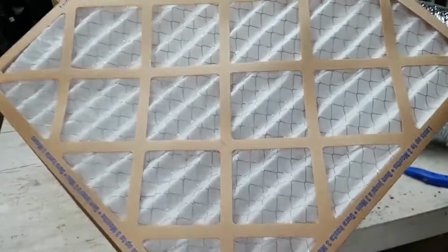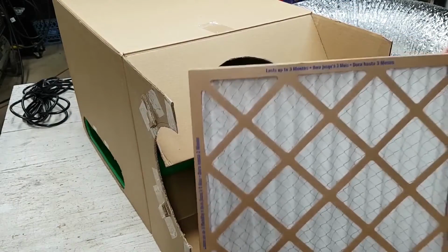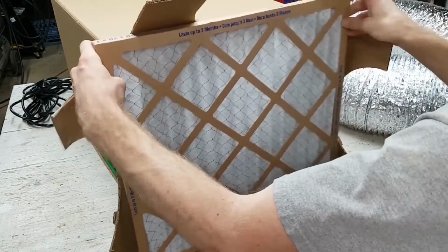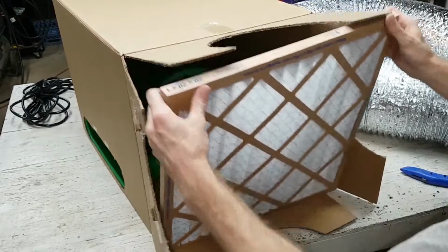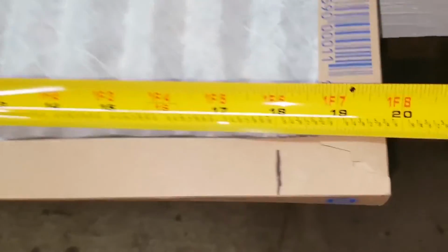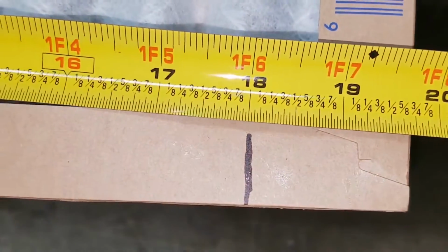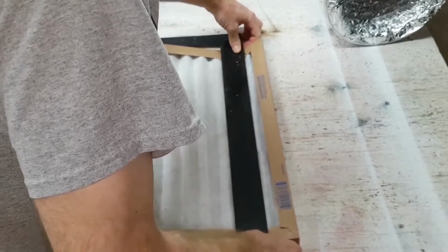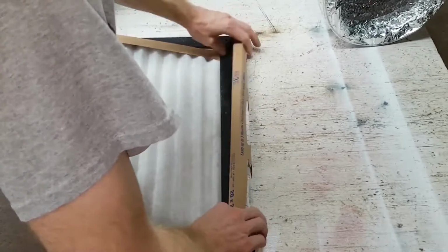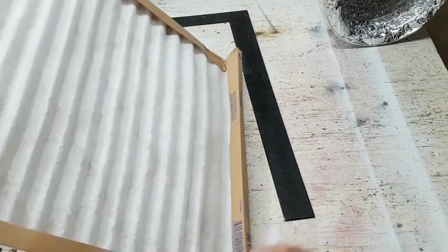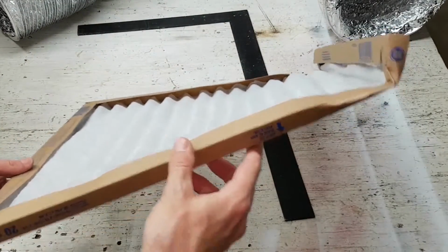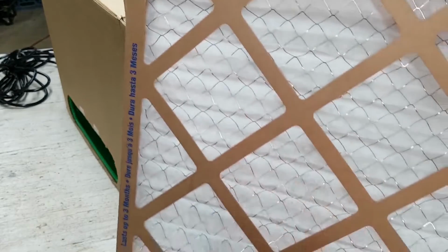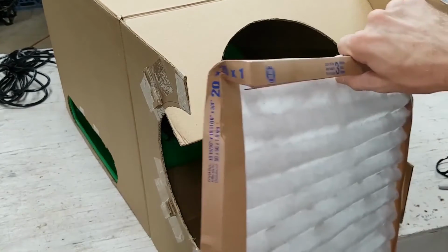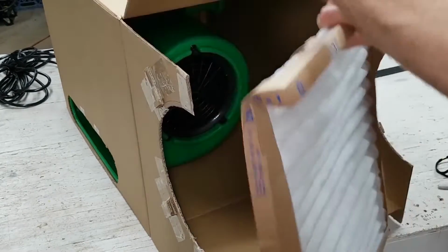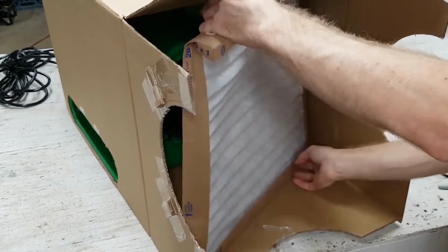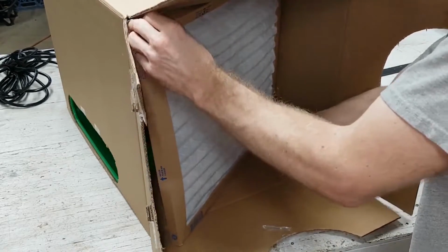A 20-inch by 20-inch by 1-inch MERV 7 furnace filter should fit in the box after some folding. It's marked at 18 inches to fit the box and then folded like so. It's ugly but should work fine. The reinforced side of the filter goes toward the blower. It only fits in at an angle. One end will be jammed into a corner of the box while the other end will be secured with tape.